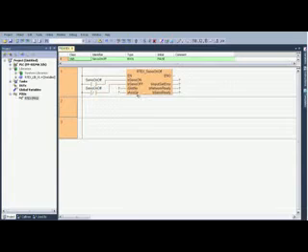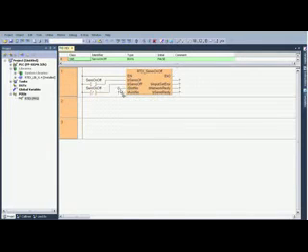Now the last thing I need to do for this function is to tell it which slot number I'm working in and which axis I want to reference. So the slot number is the position where the RTEX expansion module is in relation to the CPU. The first slot to the left of the CPU is zero and that's where this is. So I'm going to click zero. Axis I'm going to select one for the first axis. And everything on the right hand side I do not need, so I'm going to highlight it all and hit delete.